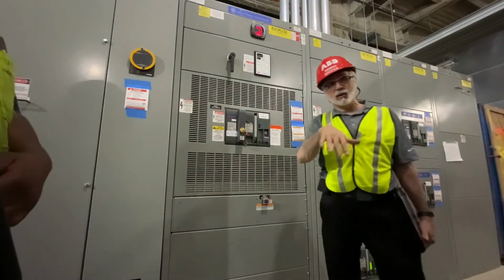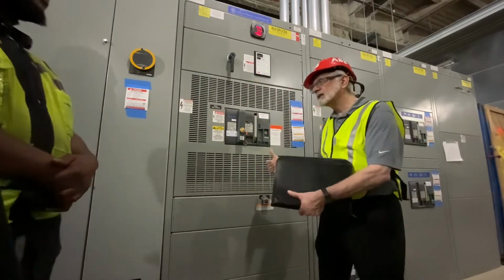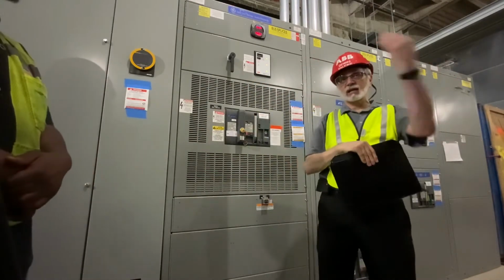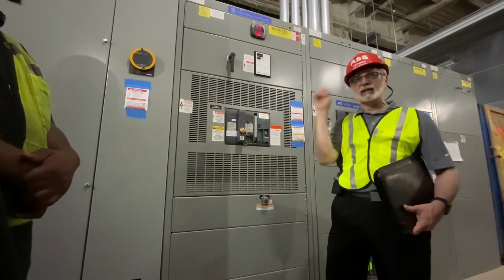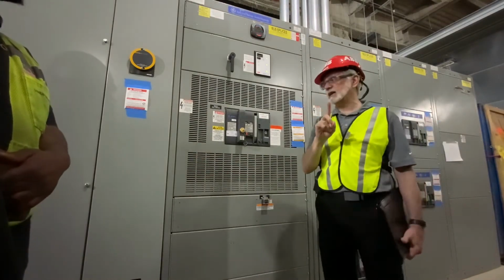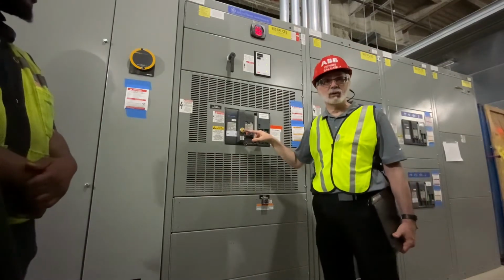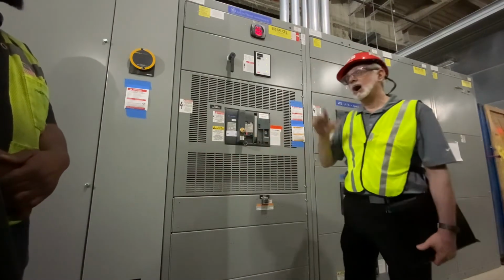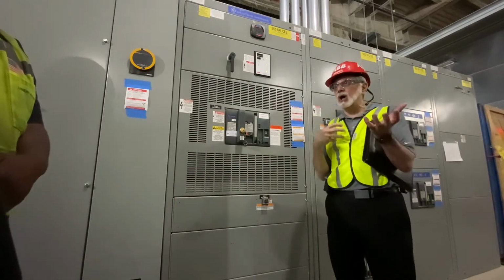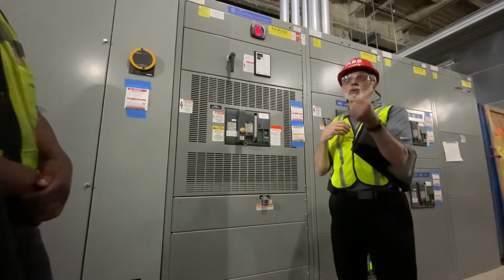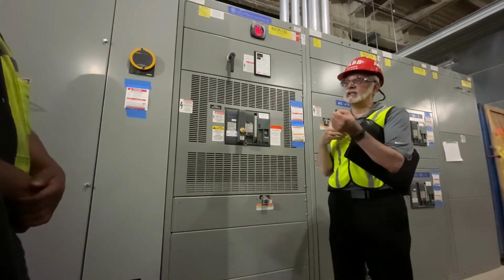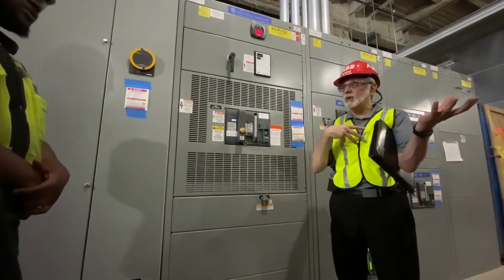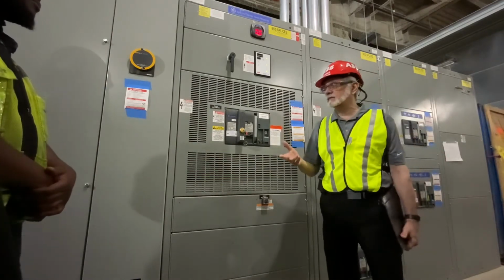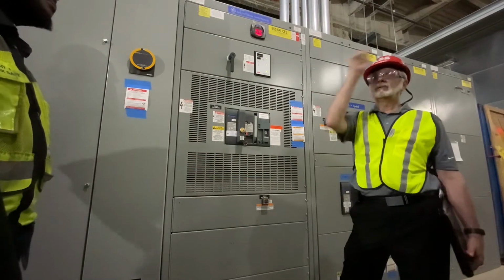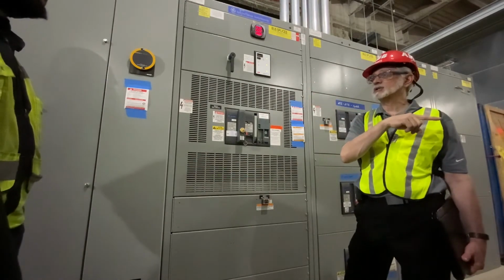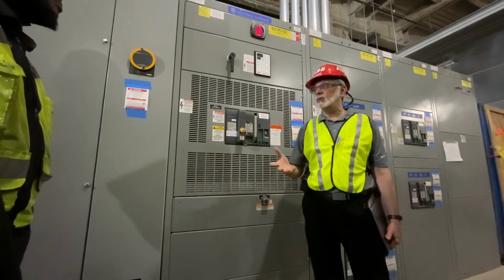Just like the equipment we had downstairs, where I have one side of the equipment feeding one part of the building and the other side feeding the other part of the building, this is set up the exact same way. The difference is this has a mechanical key interlock. Unlike downstairs, where if you saw a loss of power from Pico and the auto manual was in the auto position, it would automatically do the throw over, if for some reason you needed to do a single-ended situation up here, this would be a manual step.